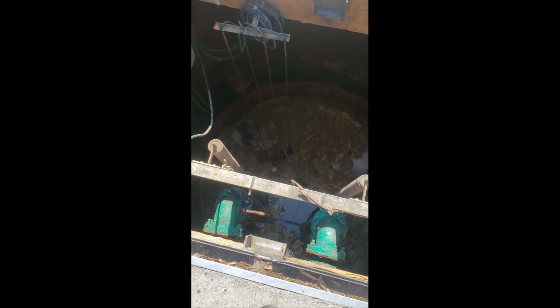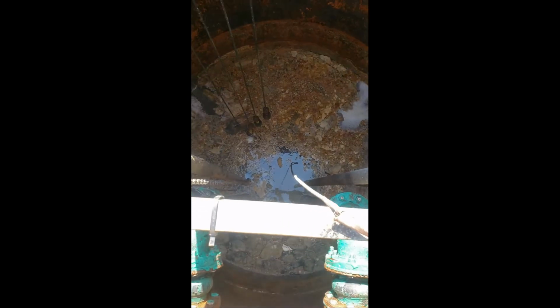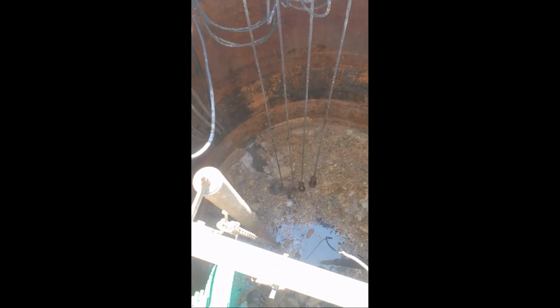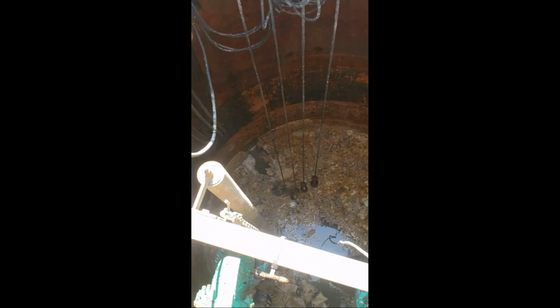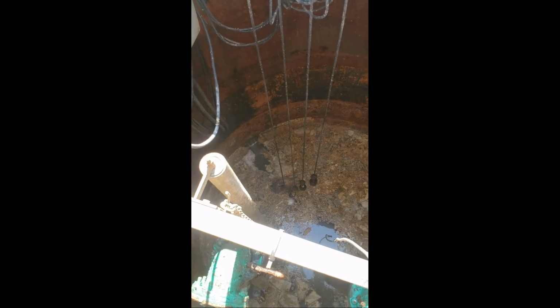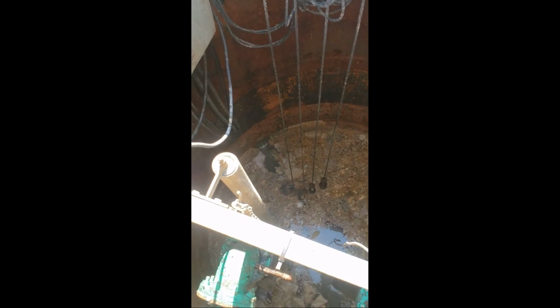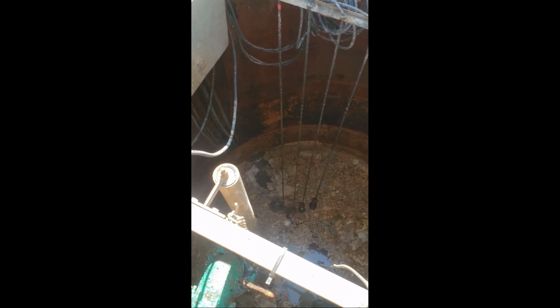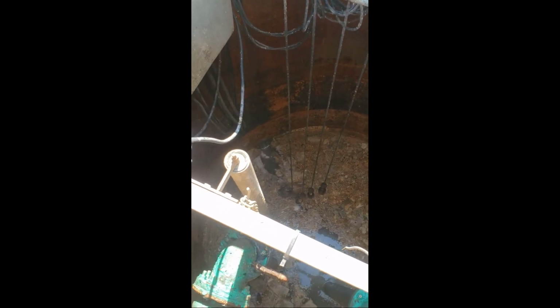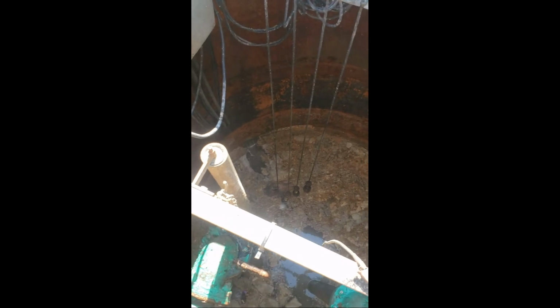As you can see, we've got all the fats, oils, and grease on top there. This one's controlled by floats — we've got 4 different floats: one to start the lead, one to start the lag, one to shut the pumps off, and finally the highest one is our high level float. We do not want that one to trip; if it does, we will get an alarm.